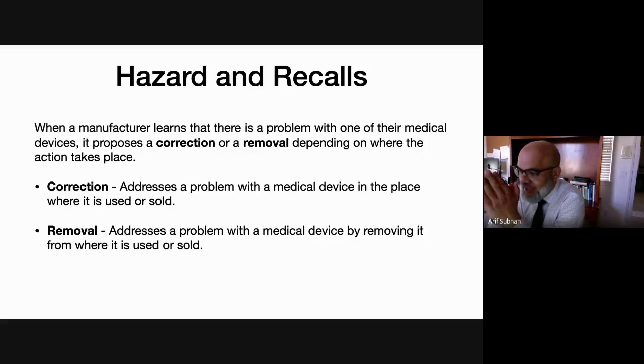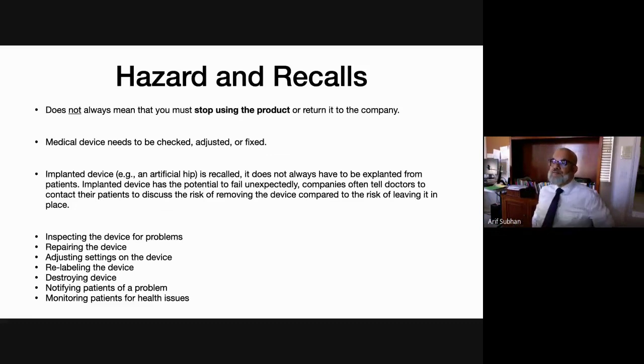So correction obviously is that the device is still there, but you would do a correction to it, maybe a software upgrade, maybe repairing that equipment that is subject to a recall, or replacing a component of that device. A removal obviously is the extreme where you feel like the problem is so severe that it cannot be used on patients, so that has to be addressed by removing the equipment. And again, keep in mind, when it says hazards and recall, it does not always mean that you stop using the product or return it to the company. It has to be either checked, adjusted, or fixed.